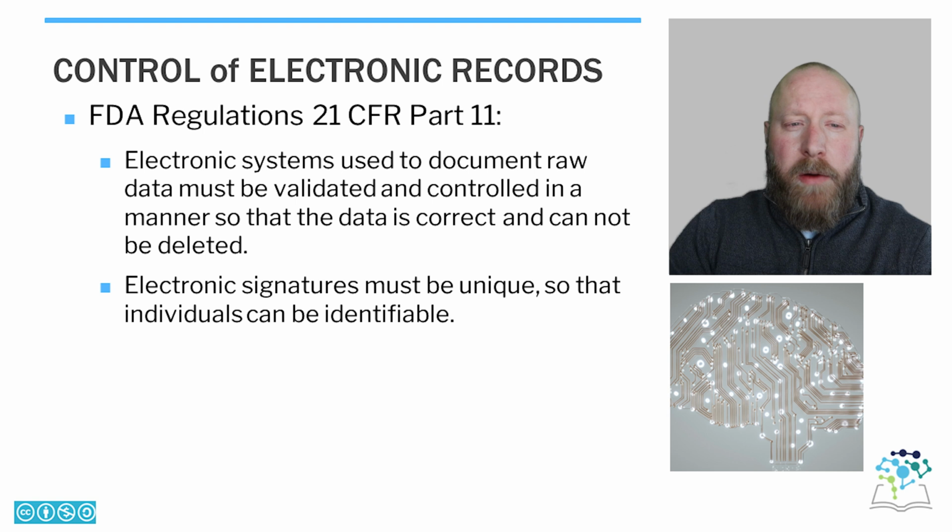Now, that is it for the GLP regulations. There is one more element that you will be getting if you do a GLP study, and that is adherence to 21 CFR Part 11, which is electronic data controls. As the industry has gone pretty much all digital, the FDA did have to establish regulations to control the actual flow and accuracy and data integrity of digital data. That is 21 CFR Part 11. These regulations provide a framework for electronic data and electronic signatures, and also provide requirements for validation, which is huge for the industry now. So I do recommend reviewing those parts of the regulations if you intend to do a GLP study as well.